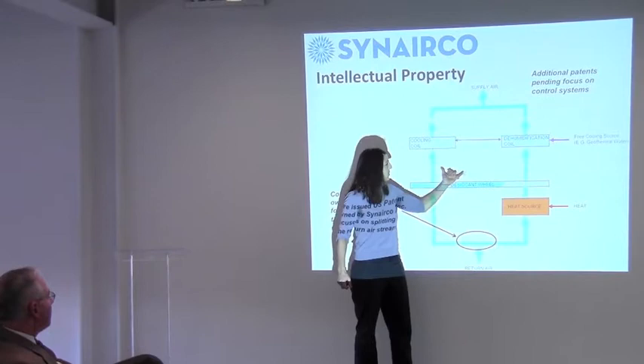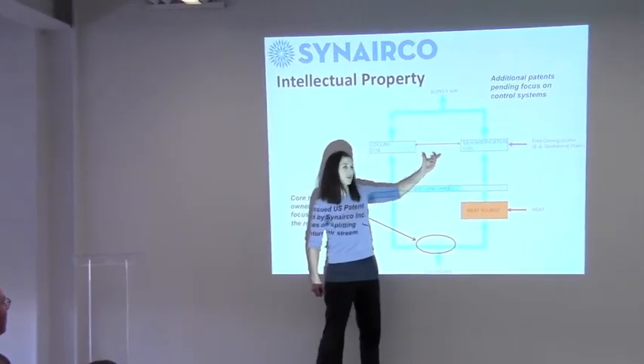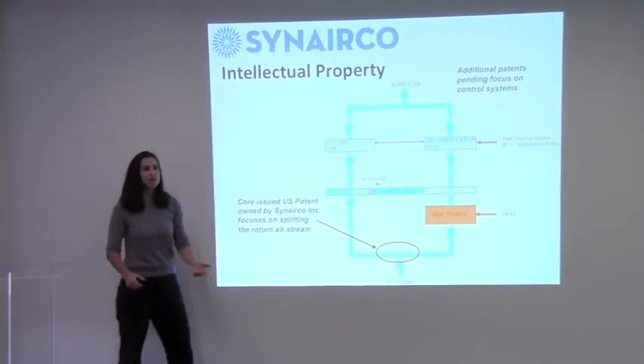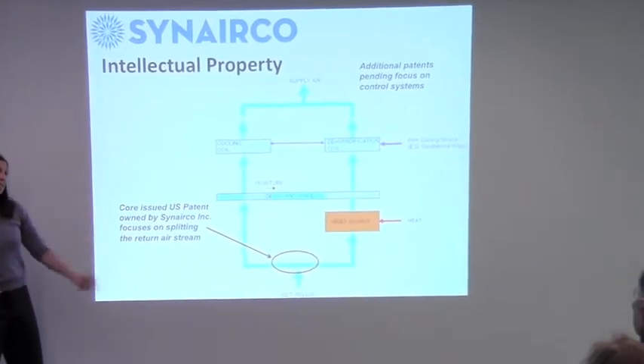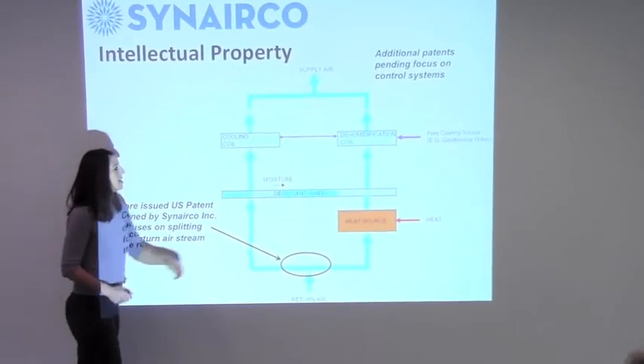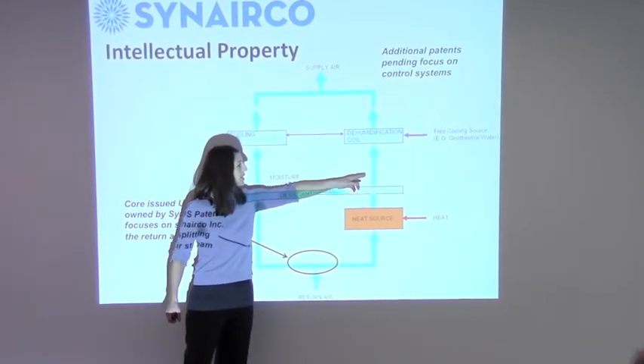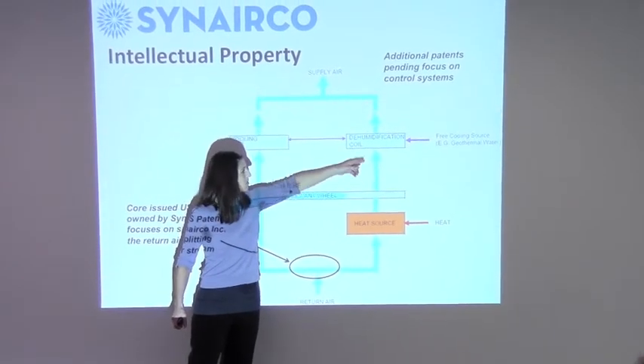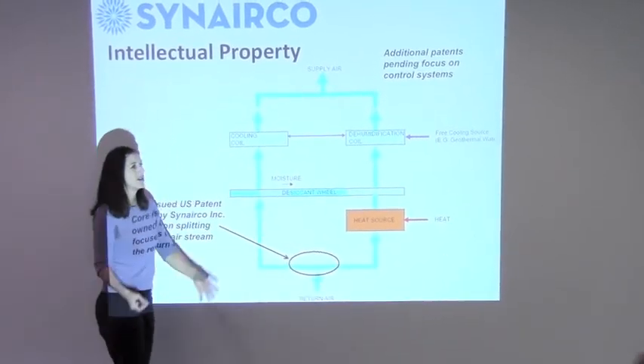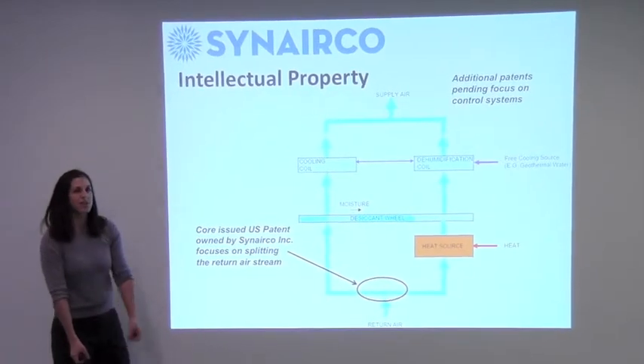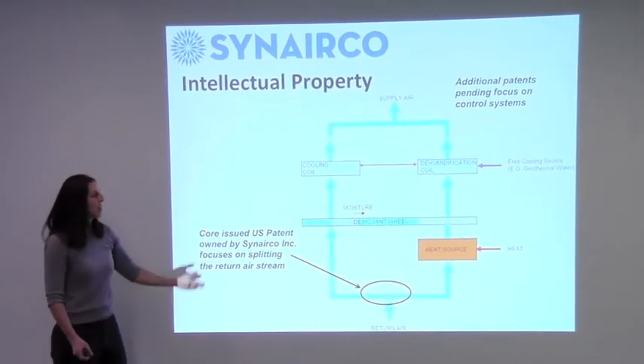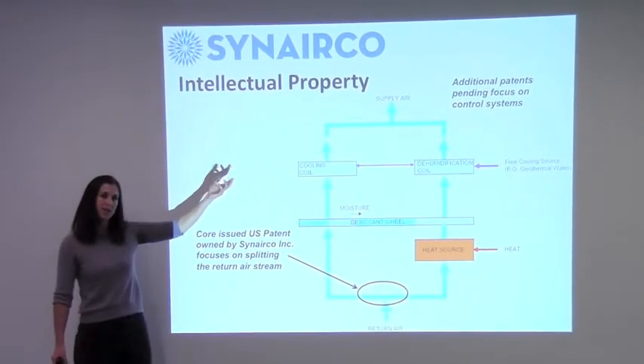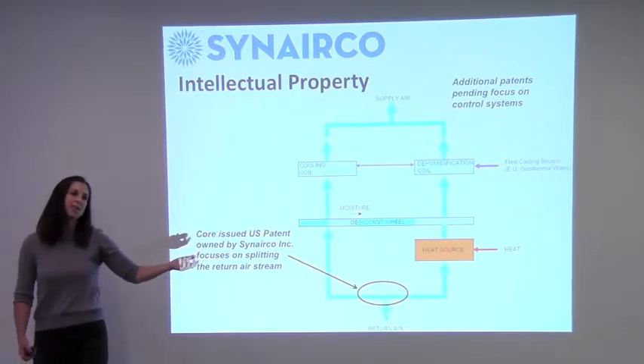So now we pass both airstreams over cooling coils fed with groundwater, a groundwater loop at about 60 degrees. Because this airstream was so heated and saturated, when it passes over that 60-degree cooling coil, the humidity falls right out and goes down the drain. Now we have 60-degree dry air we can send back to the building.